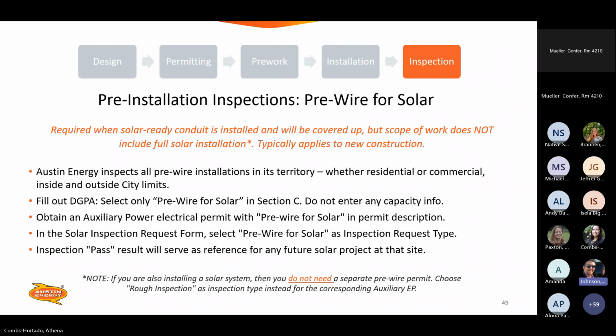Obtain the auxiliary permit with pre-wire for solar in the description of work. In the solar inspection request form, select pre-wire for solar as inspection request type. And it's basically a type of rough inspection. We're just going in while the walls are still open. Please have the walls still open and ceiling open. And then we can just look for the conduits or wires or cables that are being run for this. The inspection pass result will serve as a reference for any future solar projects on that site once somebody comes in to do the final build out of the actual PV system. All right, next.